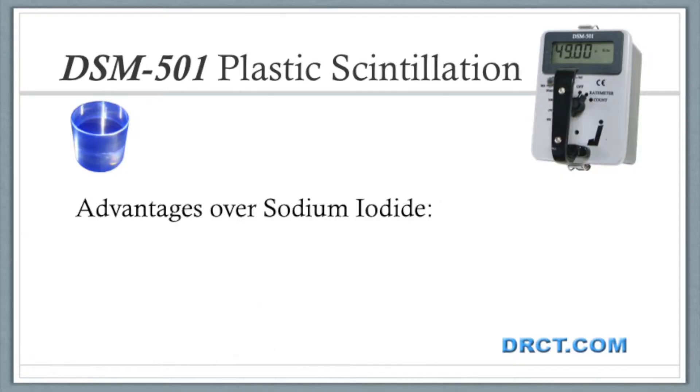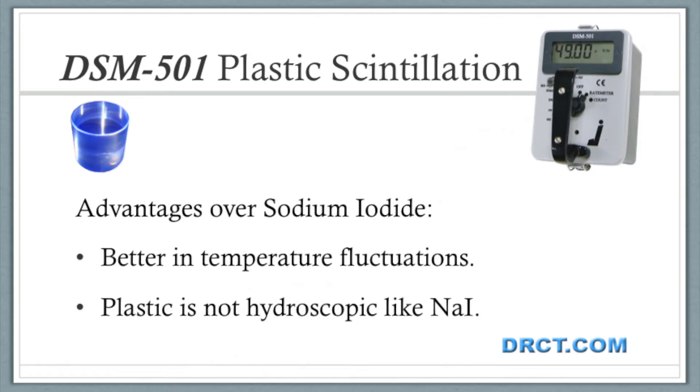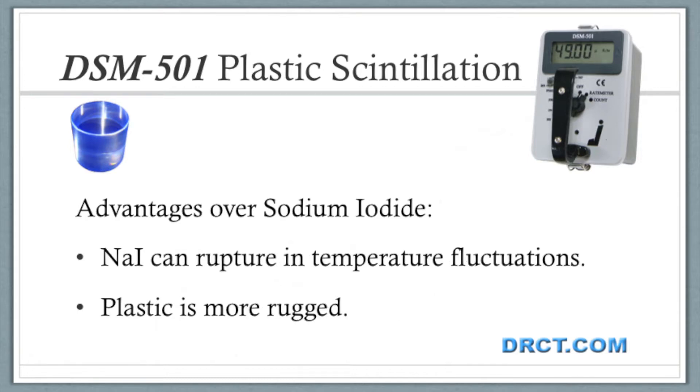The DSM-501 plastic scintillation crystal has advantages over sodium iodide in certain applications. Plastic is less dense, less expensive, and better in temperature fluctuations. For example, plastic is not hygroscopic like sodium iodide. Sodium iodide can crack in temperature fluctuations due to absorption of moisture. Plastic crystals are thus more rugged.